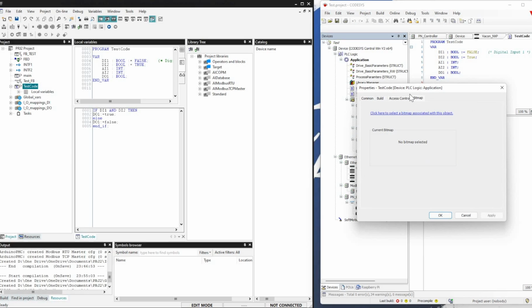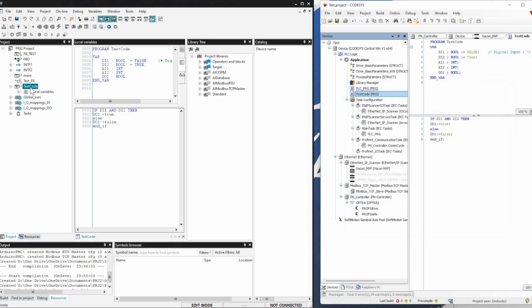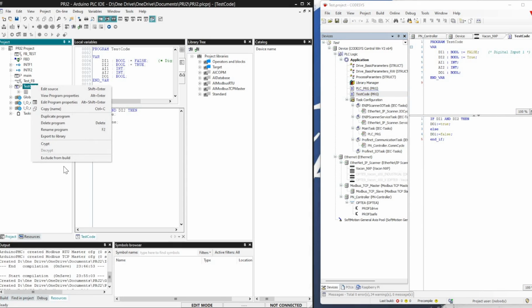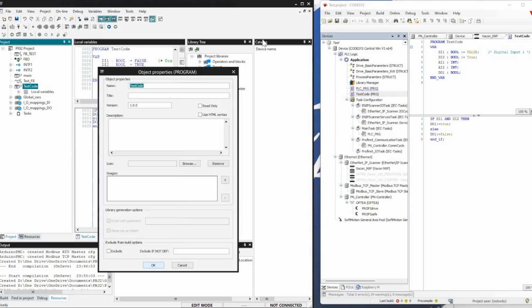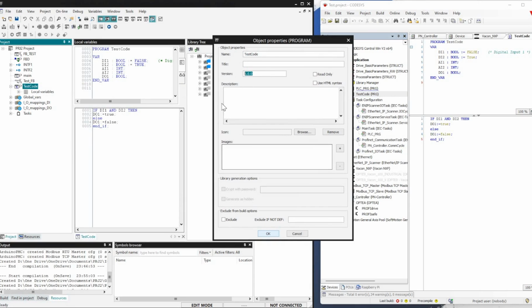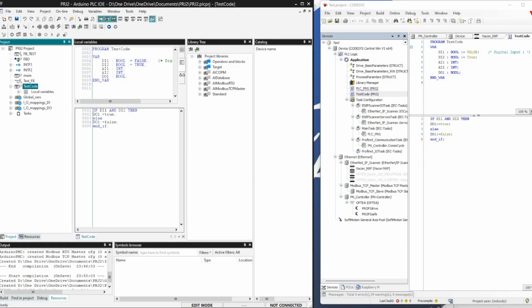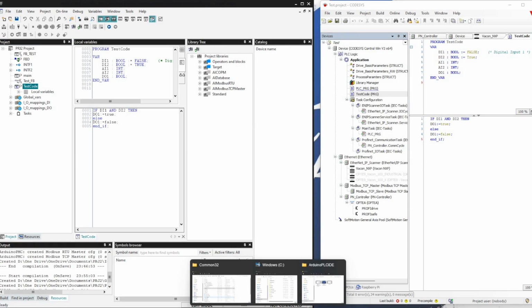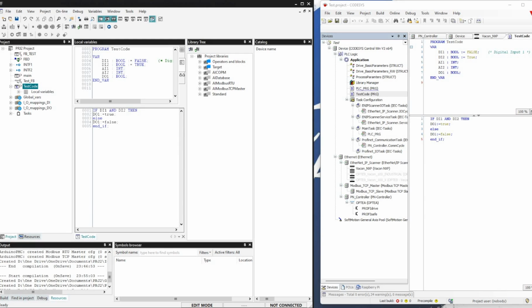The one thing which is different here is that for every task or every program they have a version number defined, and I think they need to improve that. This was fine for the number we are giving, but now the OT world is converging towards versioning and putting code into Git and getting version control from there.